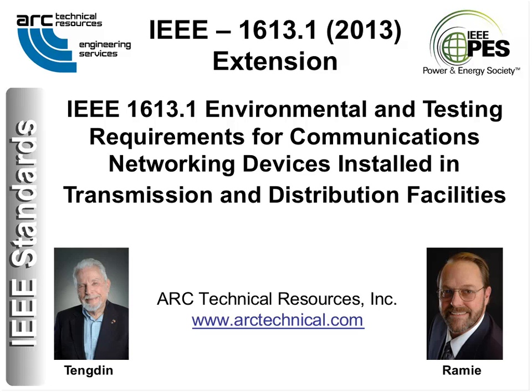And especially now with integrating renewable energy on the distribution system, those intelligent points are going further and further out of the substation. So there's even less protection against electromagnetic interference. That's why we called out pretty severe levels out in Zone B, out in distribution. And we did no breaks to the smart meters, the COM cards inside the meters. They have to meet the same level of immunities that a cap bank controller or a tap changer for maintaining voltage has to meet. To us, it's just another communicating asset that's owned by a utility out in distribution, and it has to survive its environment.